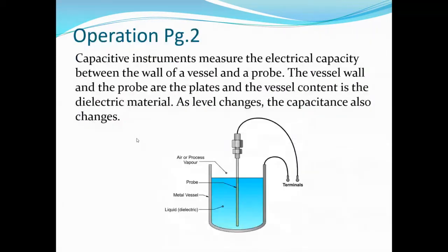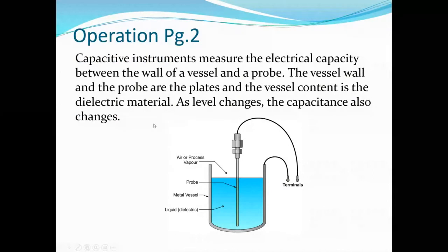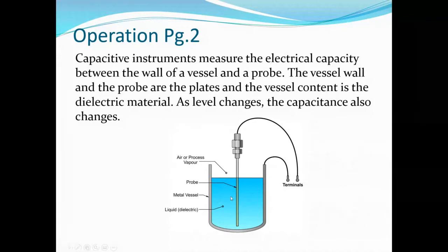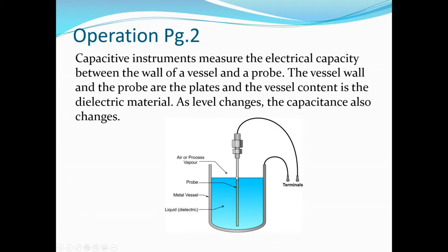Starting with Capacitance instruments. For those of you who are electricians, this will be a flashback to capacitor science — it is really just a large-scale version of a small capacitor. Capacitance instruments measure the electrical capacity between the wall of the vessel and the probe. The vessel wall and probe are the plates in the capacitor, and the vessel content — the process medium — is the dielectric material. As the level changes, capacitance throughout the range also changes, and that's how we get measurement from capacitance.